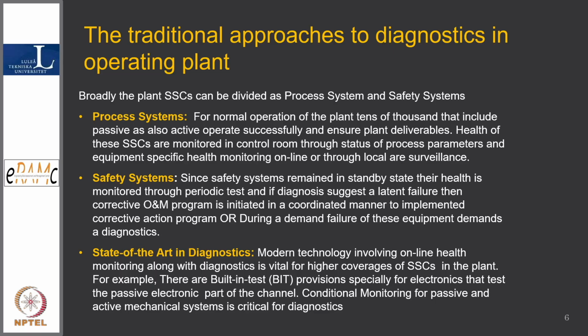Similarly, for the shutdown system, if you want to monitor leakage or a bearing, we physically do testing, called testing and surveillance. For a small period they are started, compared to full-fledged operation, and we do diagnostics on whether it is all right. If not, a complete diagnostics follows: why it happened, whether it was an oil problem, or the bearing aged, inner race or outer race issues, as I mentioned.